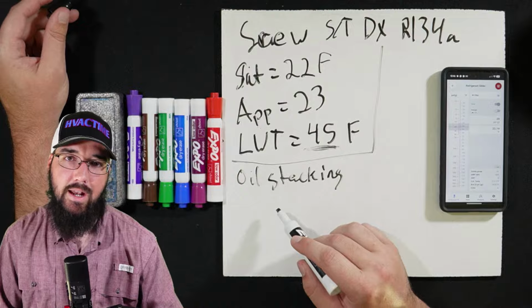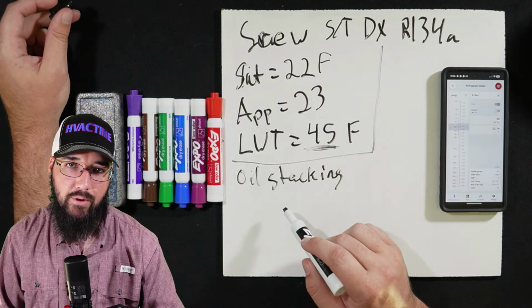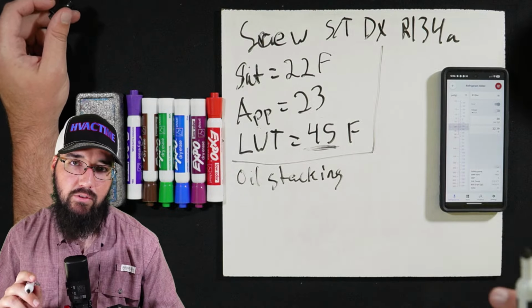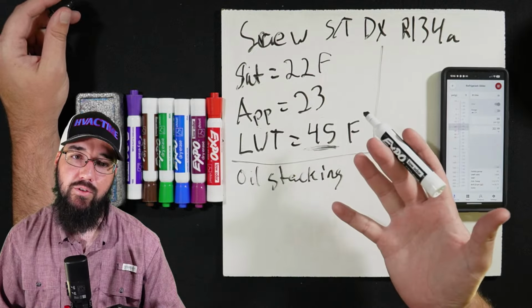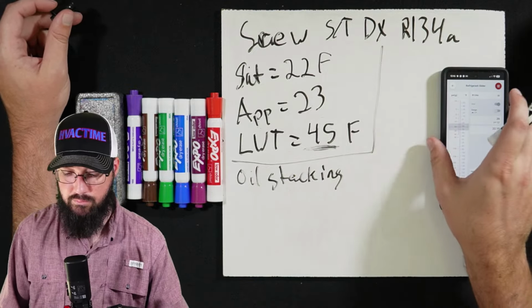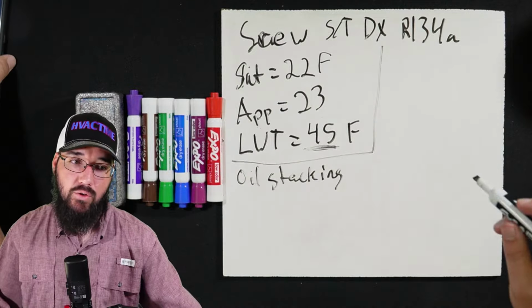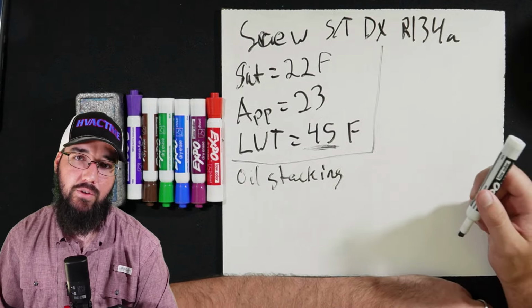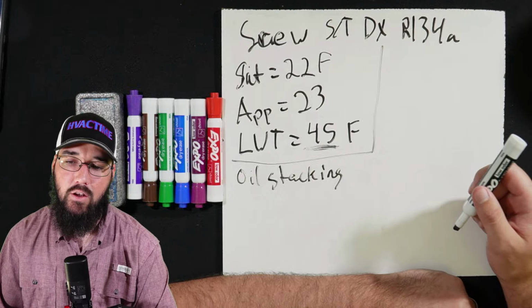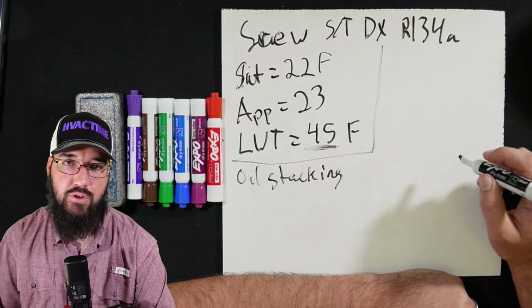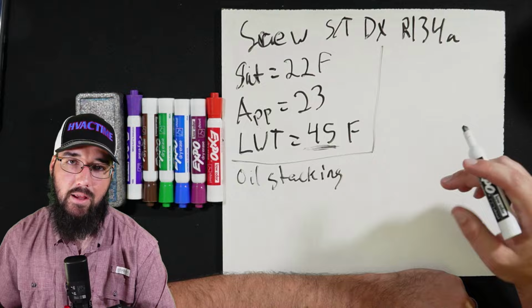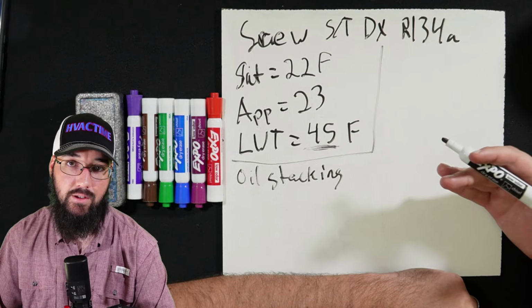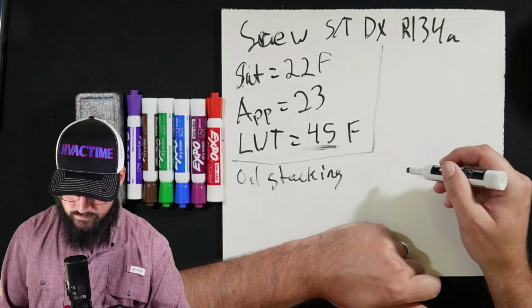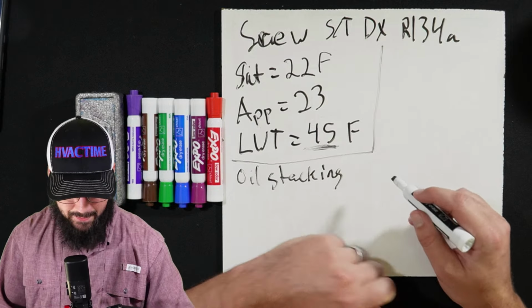One of the things that can happen with a DX evaporator, especially if we have a low load, so the compressor is not able to stage up properly and is running at a minimum load, is that it also lowers the total velocity through the machine. And by velocity, I mean refrigerant velocity. So part of what can happen, let's see.